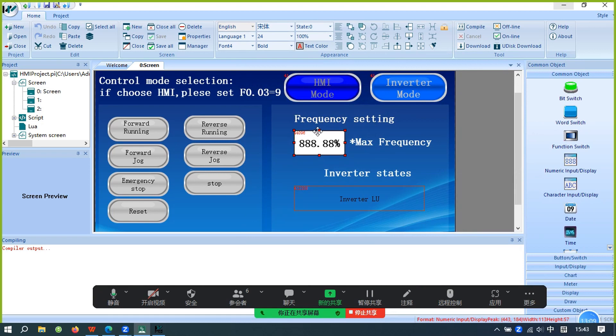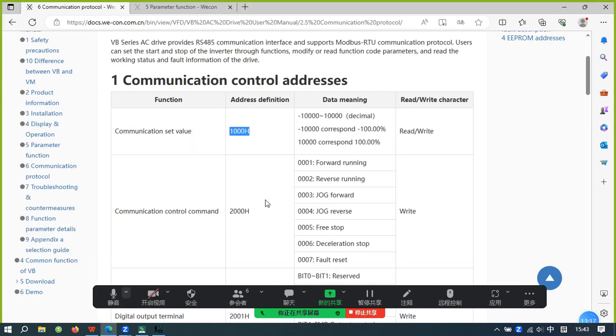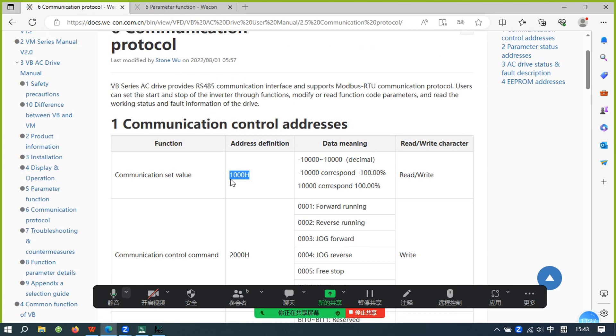This part is the frequency setting. If this address is at its default value, the range is negative 10,000 to positive 10,000, corresponding to reverse 50Hz to forward 50Hz.